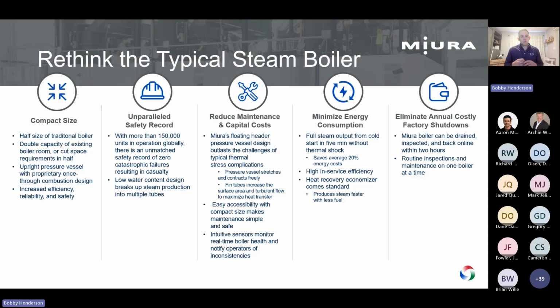It's got a built-in economizer. We'll show you the insides of the boiler here in a minute, but you're typically looking at 86, 87% thermal efficiency right out of the box without any ancillary equipment. So no stack economizers, it's all built in. And because we can be up to full steam pressure in 5 minutes, with that kind of fast reaction time, we can have more downtime. We can turn these boilers off over the weekend or turn them significantly down, so we don't have all that uptime and ramp down time like you might on a larger fire tube boiler.